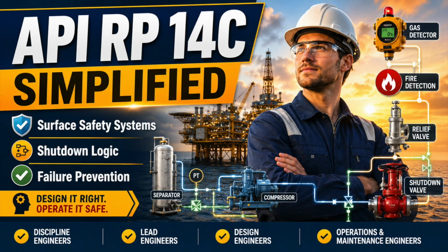First, prevent the abnormal condition from becoming a release. Second, if a release occurs, stop additional hydrocarbons from feeding it. Third, contain, drain, vent, disperse, or safely dispose of what has already escaped. Fourth, prevent ignition. Fifth, detect fire or hazardous gas quickly enough to force the facility toward a safer state. Sixth, prevent a local equipment failure from propagating across connected systems.